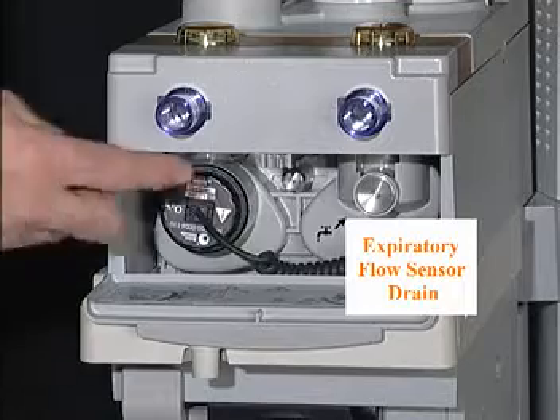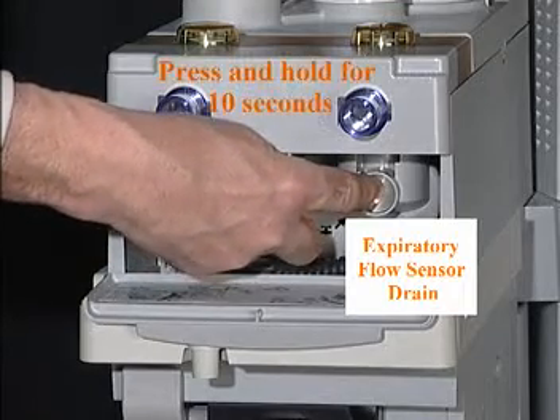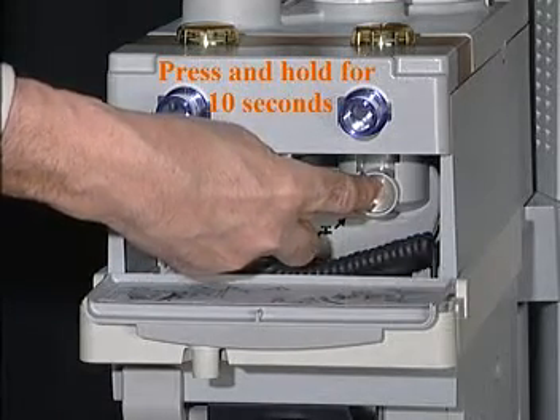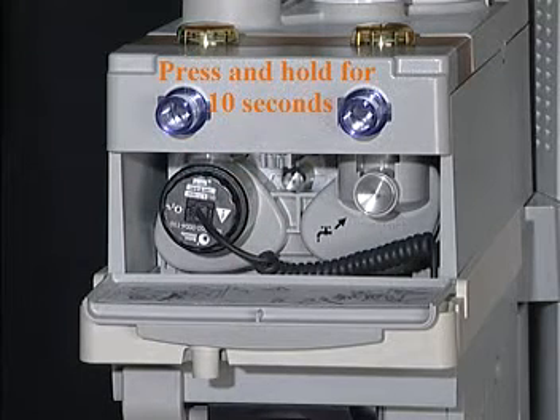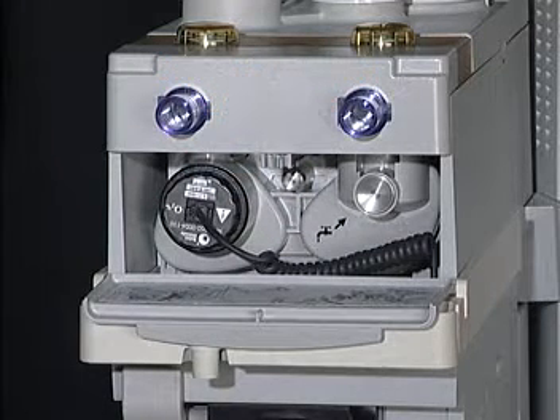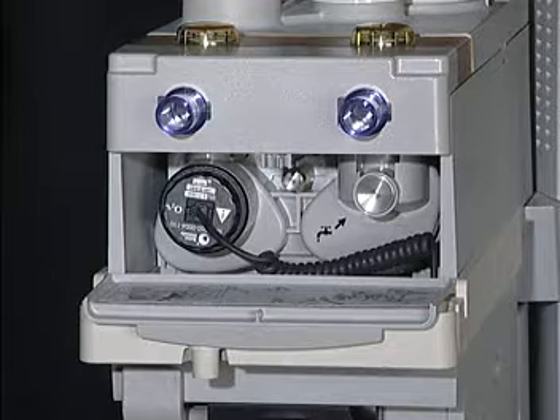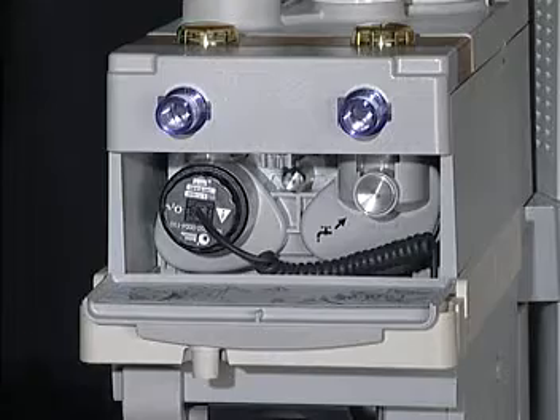In this view, you can also see the drain button for the flow sensor reservoir. Cases of long duration, in colder rooms, and/or under low flow conditions can lead to water buildup in this reservoir. Pressing and holding the button for 10 seconds periodically during the case allows the reservoir to drain into the absorber.